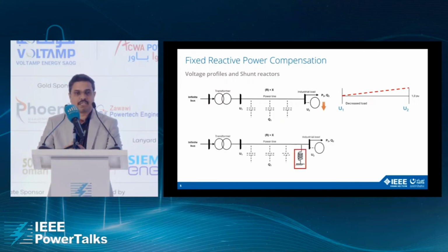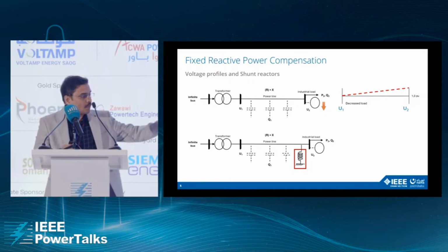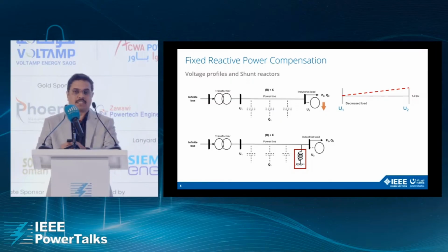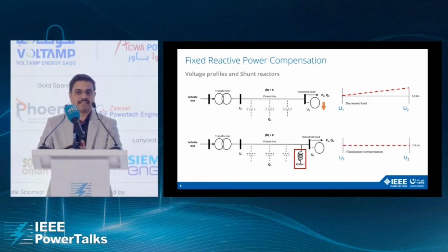One of the easiest solutions to compensate the imbalance of reactive power is to have a shunt reactor connected very close to the load centers. This shunt reactor consumes a part of the reactive power generated by the system. So here, the total reactive power generated in the system is partially consumed by the shunt reactor plus the industrial load. And again, in this static compensation scenario, we have the total voltage between the sending and the receiving end constant, because we are able to balance the total power using a shunt reactor.